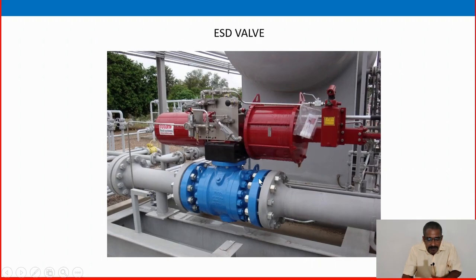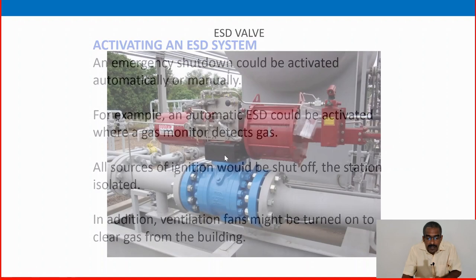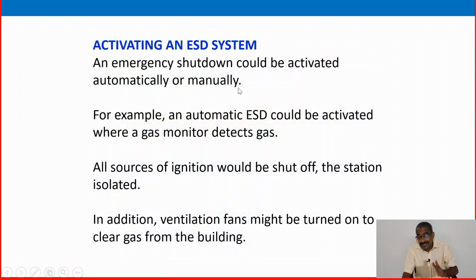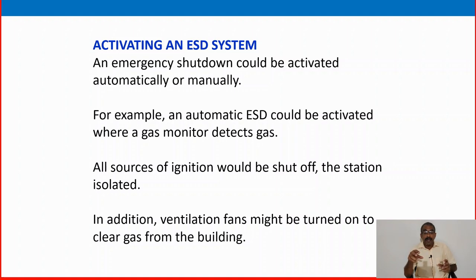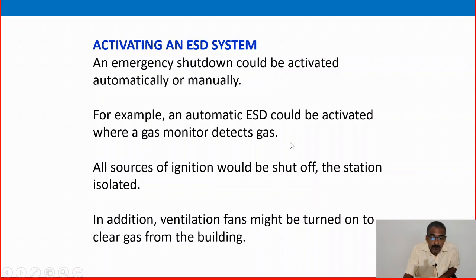This picture is taken from a separator — the separator feed line, pressure outlet line, or liquid outlet line. If the pressure is high, the ESD valve will close. The system is connected to a pressure switch high-high or level switch high-high. Once activated, the logic is activated, the entire loop is connected to the pneumatic system. The solenoid is electrically disconnected and de-energized. Immediately the connected solenoid de-energizes, and the ESD valve goes to fail close.